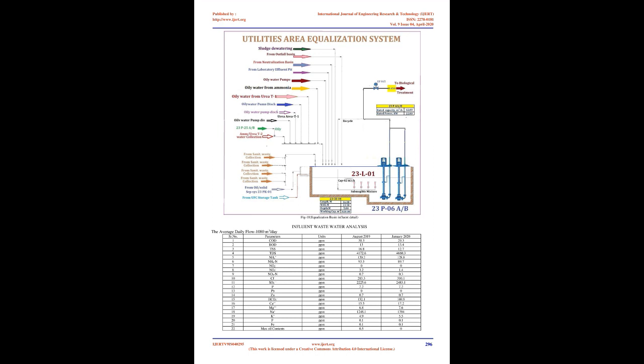The centrifuge is provided with vibration switch, temperature transmitters for the main bearing and bowl speed measurement. To maintain consistent cake dryness, the centrifuge is operated on the constant torque principle, which varies the differential speed between the bowl and the scroll to keep the scrolling torque constant during operation when the solids loading varies due to fluctuations in feed sludge concentration.